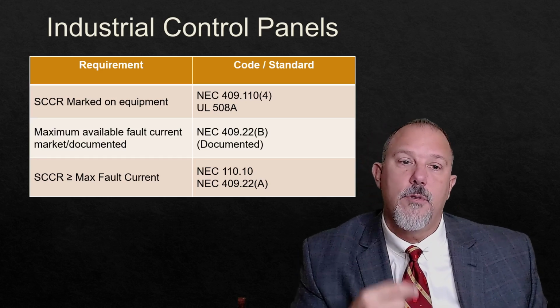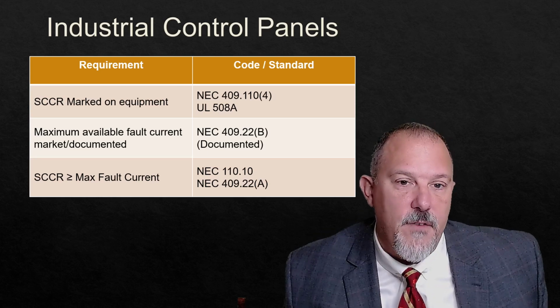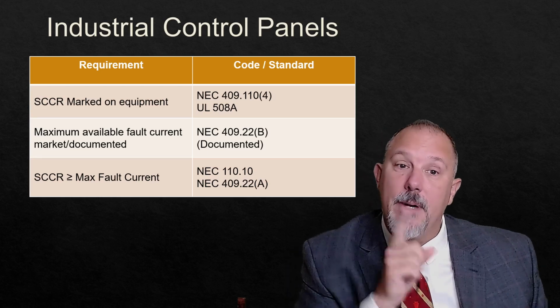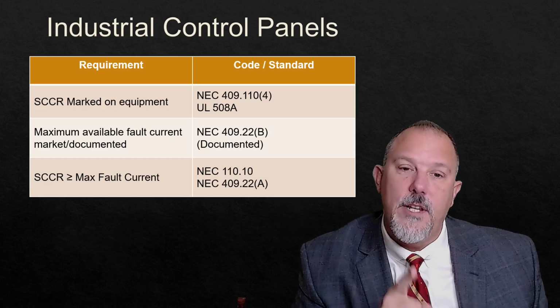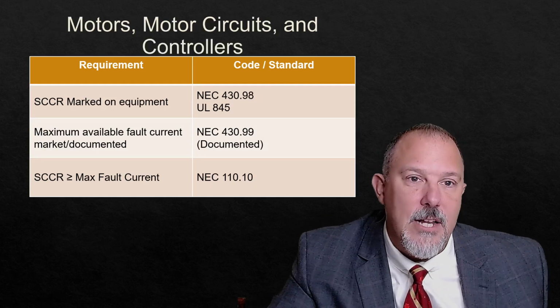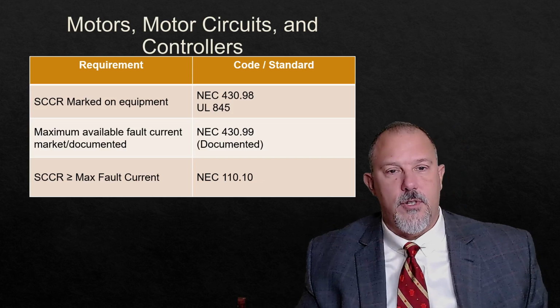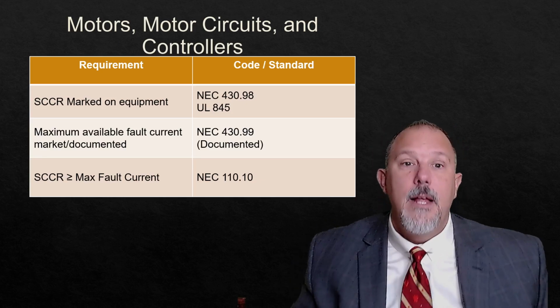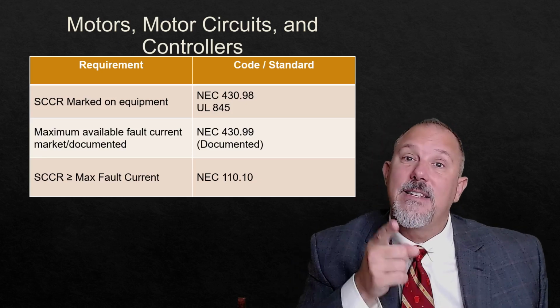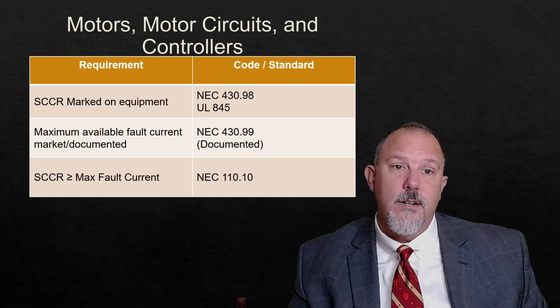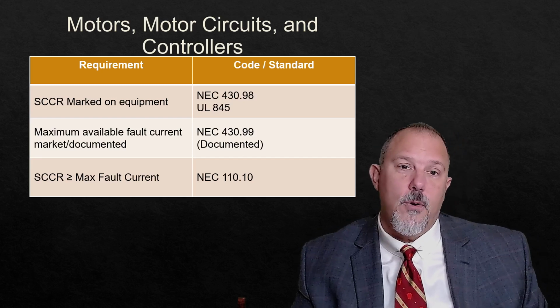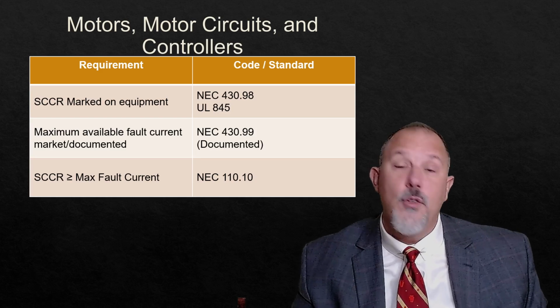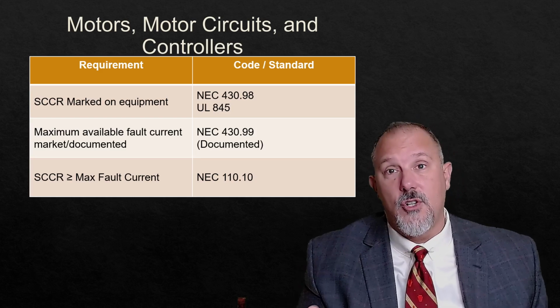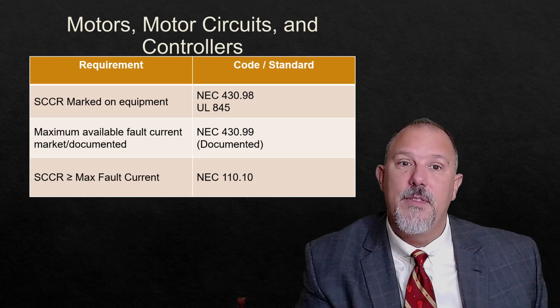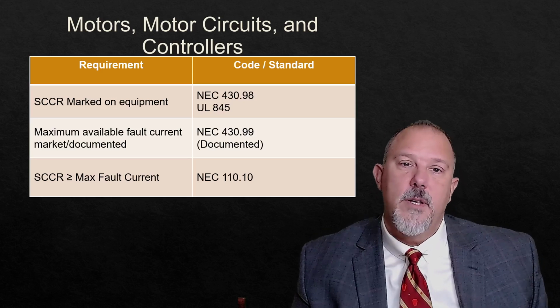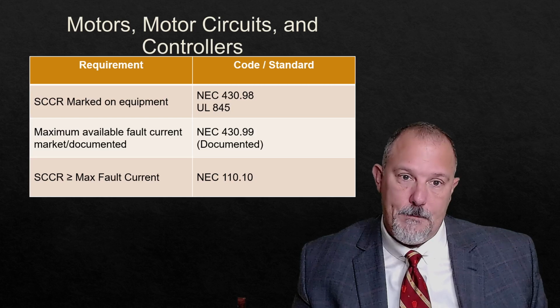And you have to make sure the short circuit current rating is greater than the maximum fault current, and that's because of 110.10, but also because of 409.22A. Take a look at motor circuits and controllers. Now you need to document the available fault current, the short circuit current rating. If it's a listed motor control center or a motor circuit controller, whatever, it's a UL 845, you're going to be required to mark the short circuit current rating on that equipment based upon the listing, but also because of 430.98.